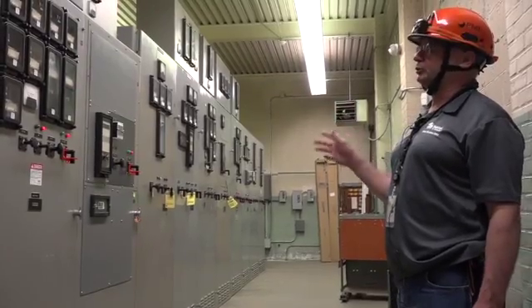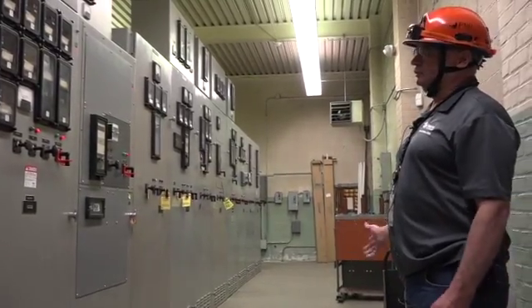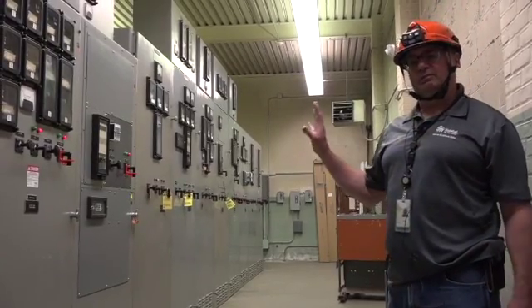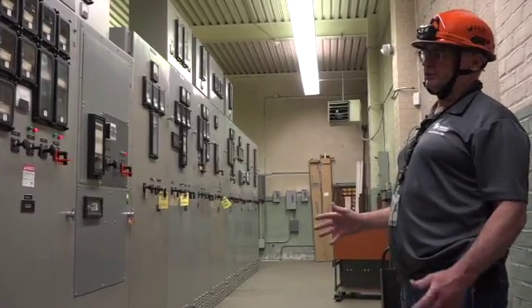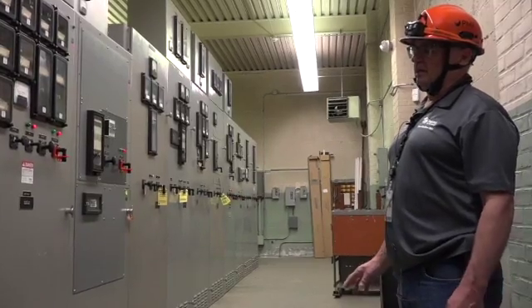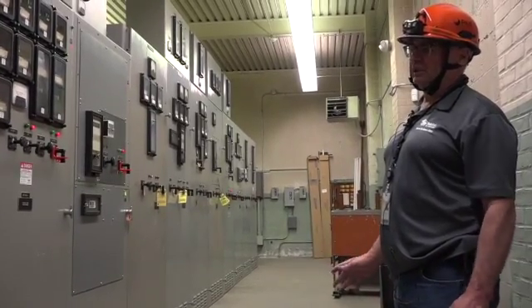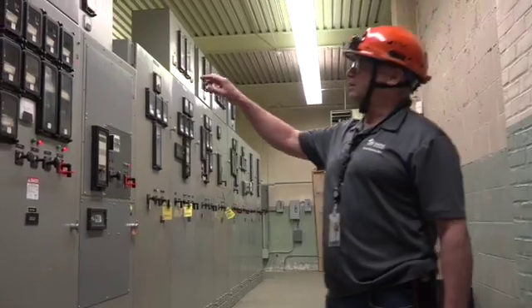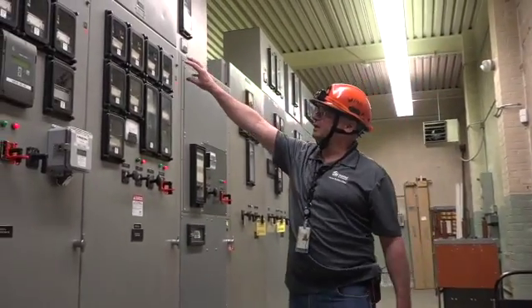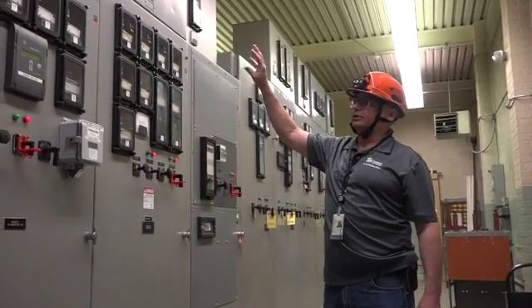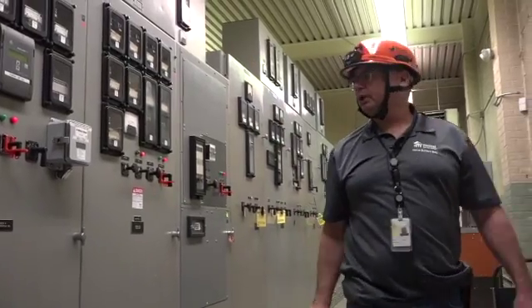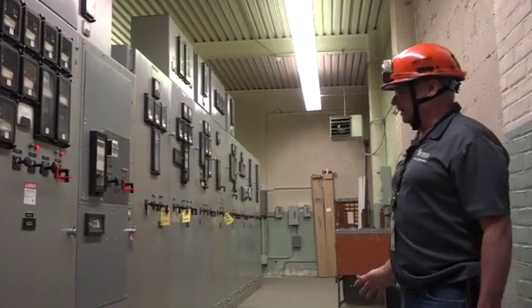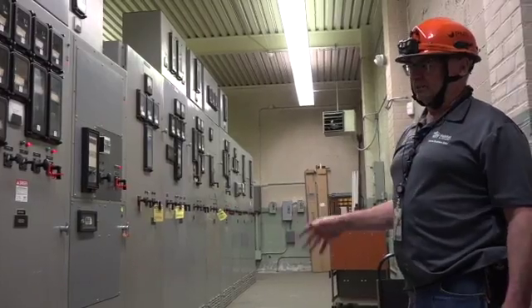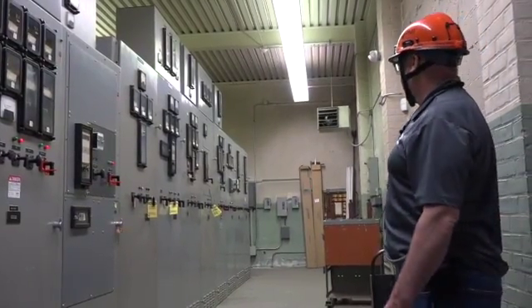For the electrical trades, there's a huge amount of maintenance that's required to maintain this type of equipment. The breakers have to be tested quite frequently. They have to be cleaned, maintained. All of these relays have to be cleaned, taken out and tested to make sure they trip correctly, so that if there is a fault, it doesn't cause catastrophic failure.